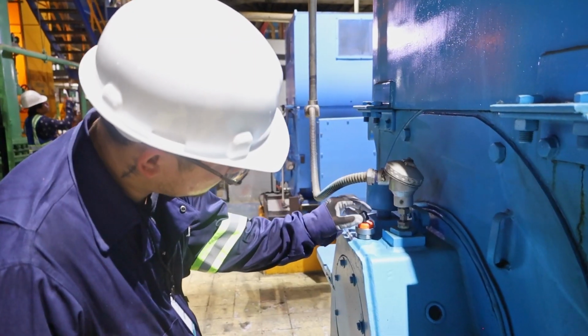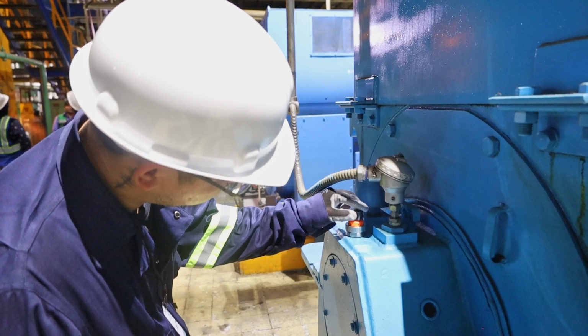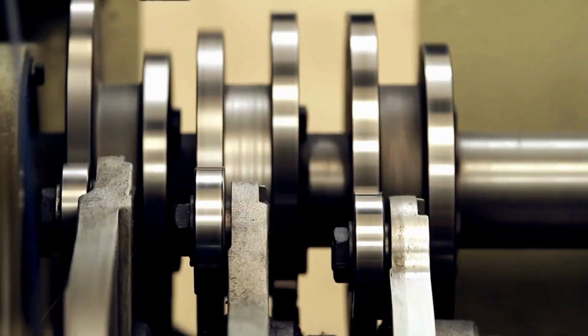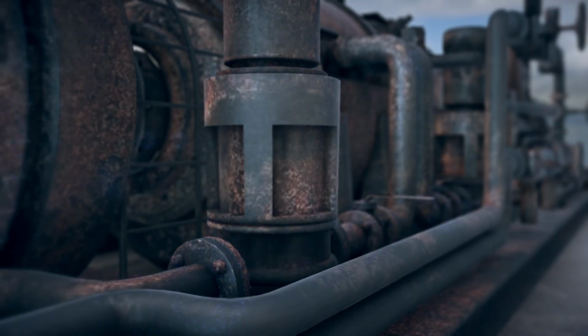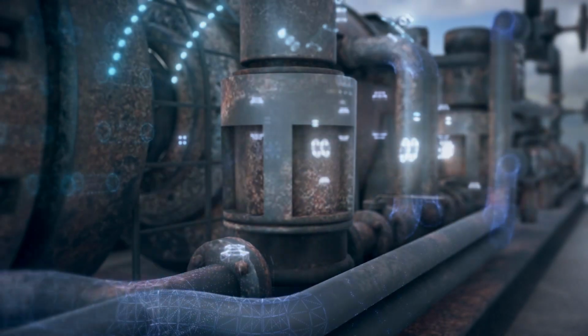correlate if inrush current is very high, perhaps that may be impacting something to do with the machine, a bearing fault as an example, or if the suction pressure on a pump or discharge pressure on a pump is very high, the engineer may very well understand that, okay, well, this is cavitation, and that helps them look at the vibration signal that may in some ways indicate that there's a problem, but when they look at it in correlation to the suction and discharge pressure, as an example, that may indicate that there is no problem, and in fact, it's just cavitation that needs to be addressed, and that's a process issue.